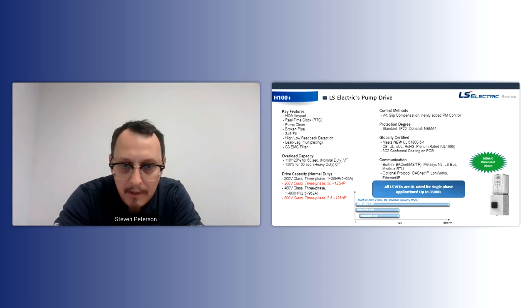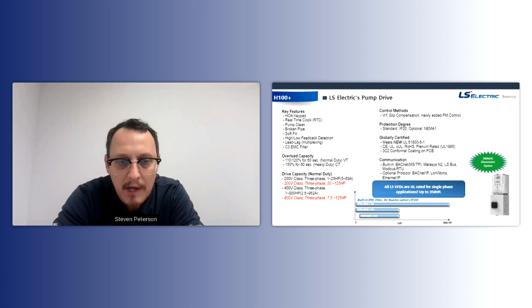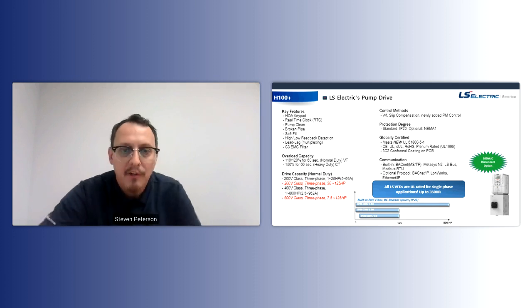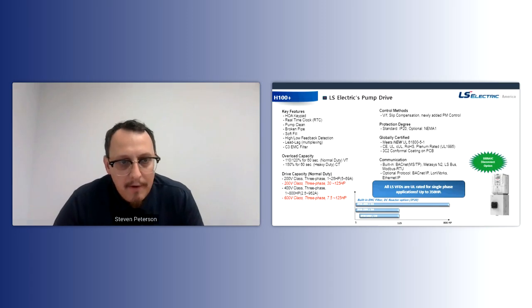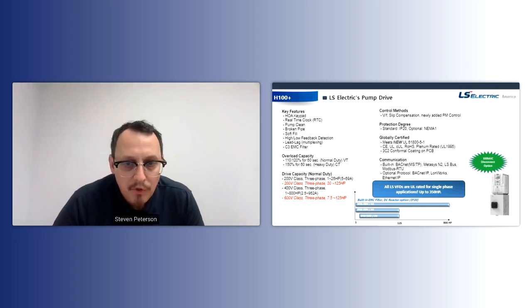And one other thing I'd like to mention, which especially with your industry you may find beneficial, is that we've done UL testing on all series drives, all capacities for single phase input. So we go up to 800 horsepower, 3-phase input on the H100 Plus. We have approximately a 50% derate. So after we tested this with UL, you could take that 800 horsepower and get 350 horsepower out of it.